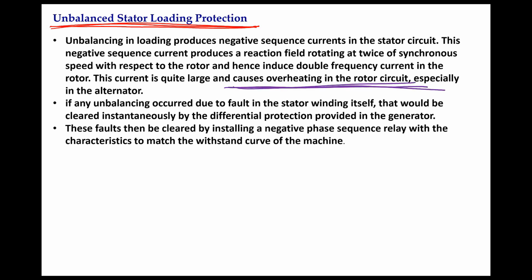Understand? If any unbalance happens inside the stator winding itself, it is cleared by the differential relay. But if the unbalance happens on the load side, that is after the stator winding, then it will not be detected by the differential relay. So in this case, this unbalanced stator loading is sensed and cleared by the negative sequence relay.